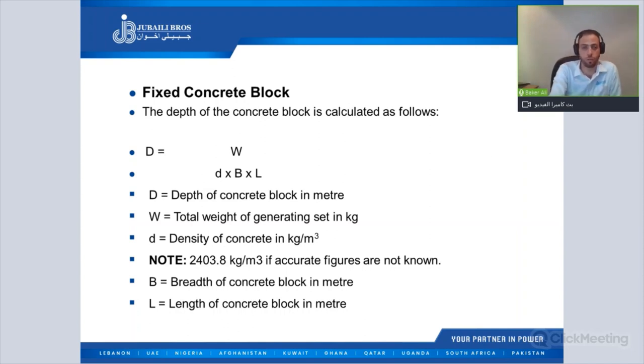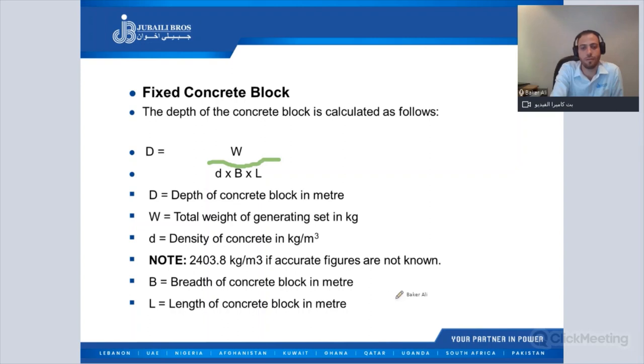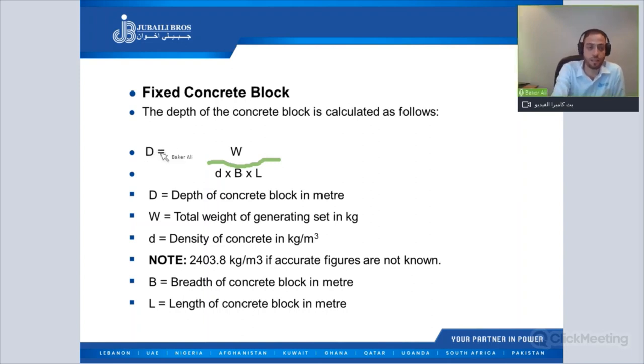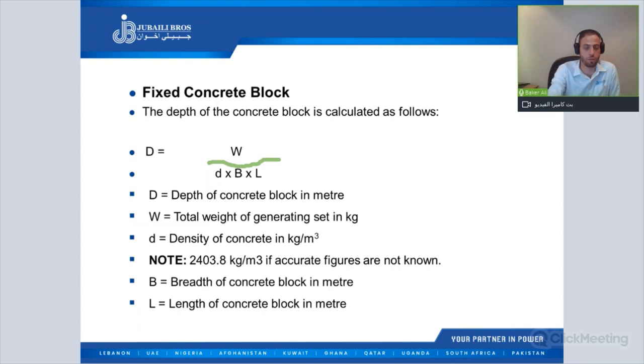The depth of the concrete foundation is calculated as: D = W / (d × B × L), where D is the depth in meters, W is the total weight of the generator set including engine, alternator, and base frame, d is the density of the concrete in kg/m³, B is the width of the concrete plot, and L is the length, both in meters. If you don't have an accurate figure for concrete density, you can use 2,400 kg/m³.